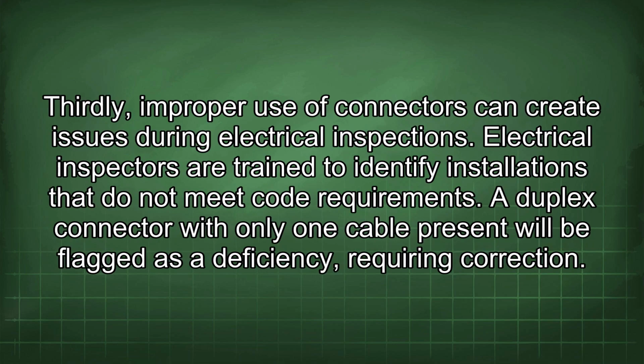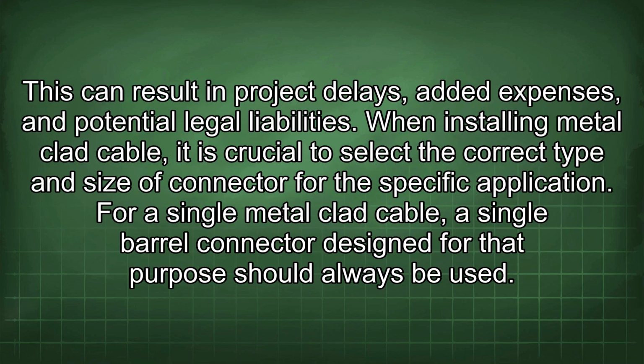Thirdly, improper use of connectors can create issues during electrical inspections. Electrical inspectors are trained to identify installations that do not meet code requirements. A duplex connector with only one cable present will be flagged as a deficiency, requiring correction. This can result in project delays, added expenses, and potential legal liabilities.